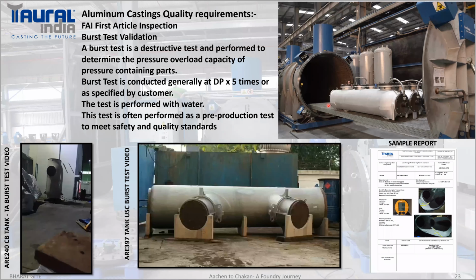This test, 10⁻⁹ millibar liter per second, confirms the stability of design pressure, where all components, 100% of serial production components, have to go through the helium and air pressure leak test. Only the first few samples have to be burst. The burst test is where the customer wants to validate their own design of the casting, the wall thickness, whether it will sustain 5 times the design pressure.